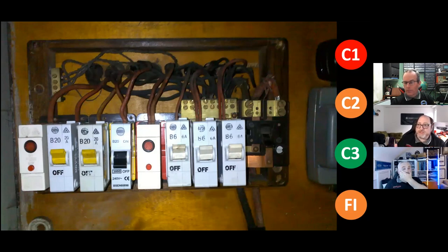And if the electrical installation is compromising your ability to properly inspect it and maintain it, it must be considered as life expired at that point, if you can't maintain it effectively. Yeah, this, I mean, one, I'd go for a C2.